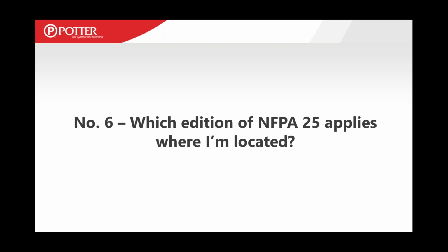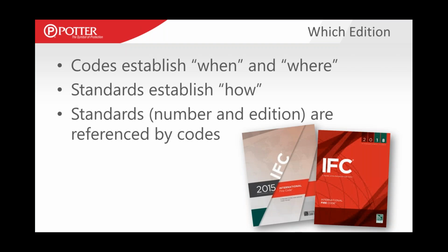We spend a lot of time focusing on new systems, commissioning and things, and that's critical. We have to get them right to start with, but there's a lot more existing systems than there are new ones. So as changes take place in NFPA 25, we have to remember all these changes apply to every system that's out there. So knowing which edition applies where you're performing work, or where the building is located, is critical. Typically, the way this works is through the codes that are adopted.